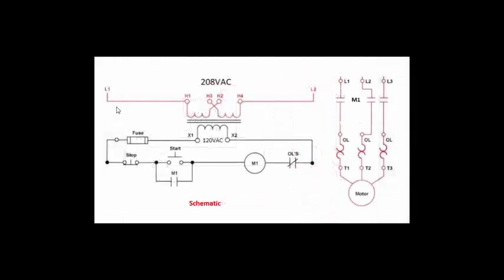So this is the schematic diagram of the same circuit, and what we have here is the transformer again, and from the transformer the fuse is next, and voltage will go through the fuse as long as the fuse is not blown, to the normally closed stop button if it's not pressed, and then to the start button, which is normally open, and voltage will also go up to the auxiliary contact. On the other side of the transformer, which would be the neutral side of the transformer, we'll have neutral going to the overload contact, which is normally closed. As long as the overload relay does not trip, that contact will be closed, and neutral will go to the coil, the M1 coil. And this is the coil that controls these three contacts here, as well as this contact.